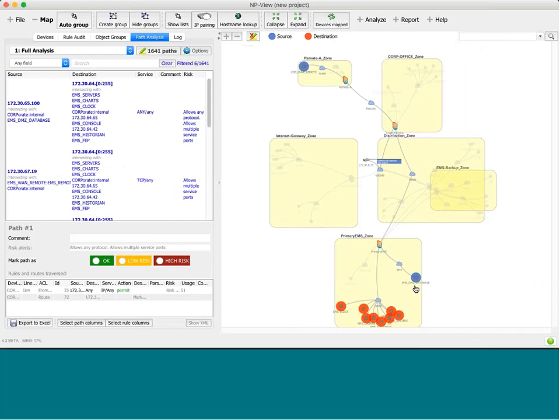One of them is coming from a neighboring network, and it's the EMS database. Another one is coming from the corporate network zone. And then a third one is coming from a remote wide area network EMS host. So those two may be okay, but that last one, which is crossing 3 different firewalls before reaching that EMS zone, may not be a good one. Like that, I may not want someone from the remote access zone to be able to get access all the way towards my most critical asset in the energy management system.